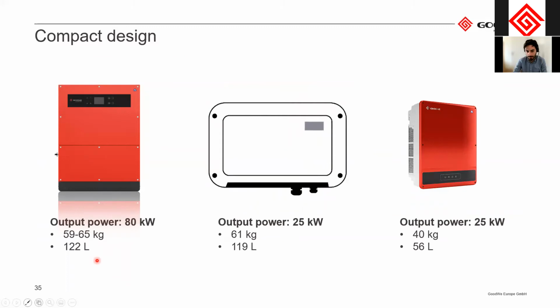Our CNI inverters also have a very compact design. So if you're comparing the output power here of 80 kilowatt, it's sort of the same as some competitors, but the competitors in the same size range have a much lower output power. And on the other hand, the output power here can be compared to our SMT inverter, which then has a much lower weight and is also about half the size.